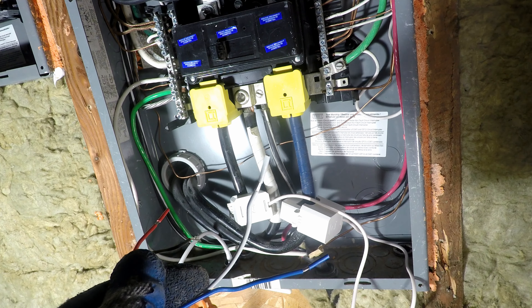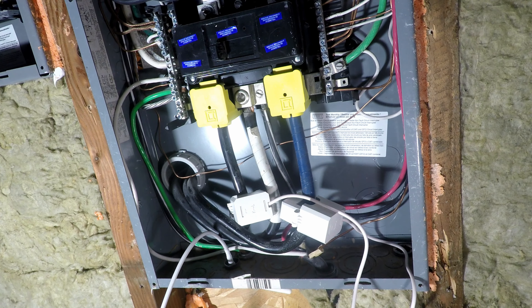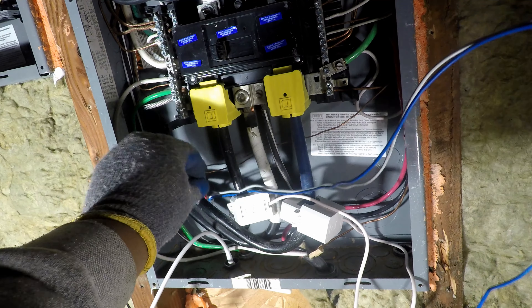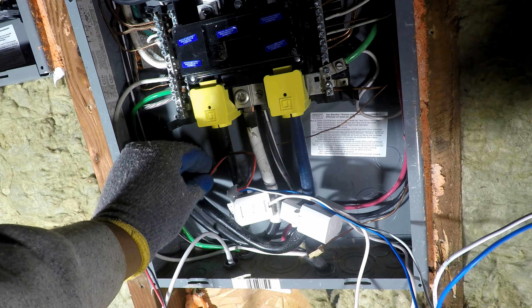Next is the installation of the wire harness. Since there are two 200-amp CTs, two wires will have to be connected to breakers — the black and the red. The blue and white wire will be connected to the neutral bus bar; regardless of configuration, the white wire is always connected to the neutral bus bar. Installation is possible even if there are no breakers available by using pigtails. Note that Square D breakers can accept two copper wires on the same breaker; however, the Emporia Vue requires each applicable wire to be on a separate breaker. Initially, both red and black wires were connected to the same breaker, which was an error.